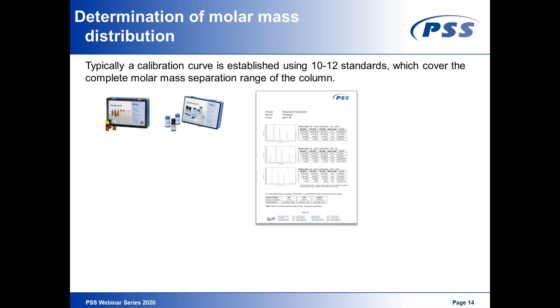Yeah, let me just go to this slide here, because I mentioned here that we have two ways for universal calibration. First of all, the universal calibration with a viscosity detector, where we actually measure the intrinsic viscosity of our standards and of our samples. In this case, we plot a so-called universal calibration curve, meaning that I plot the logarithm of intrinsic viscosity times molar mass versus the elution volume. Basically, this is hydrodynamic volume versus elution volume. So we calibrate absolutely in a way, and you can use this calibration curve for all kinds of chemistry.